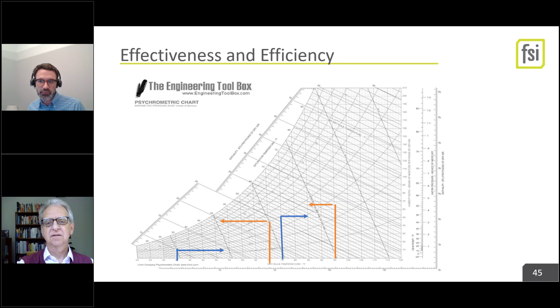So on a heat recovery unit that's sensible only, you can only move left and right on this curve. You move across relative humidity. You don't get any latent recovery at all. If you've got latent heat to recover, too bad, you don't get it. You only get the sensible part until you start condensing on the heat exchanger, which isn't always appreciated by your manufacturer. Then you get some latent. Let's go to the next one. Oh yeah, I should have said this too.